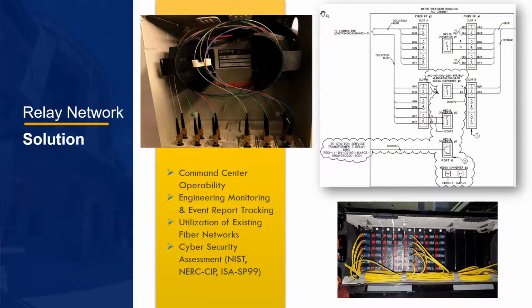The integration of the relay network provided an increase in command center operability and engineering monitoring and report tracking. With this communication network, site personnel would be able to capture event reports and perform remote relay operations from the safety of their office. Relay operation is protected by a multi-tiered password, with each tier allowing more control of the relay, with remote tripping at the highest tier of security.